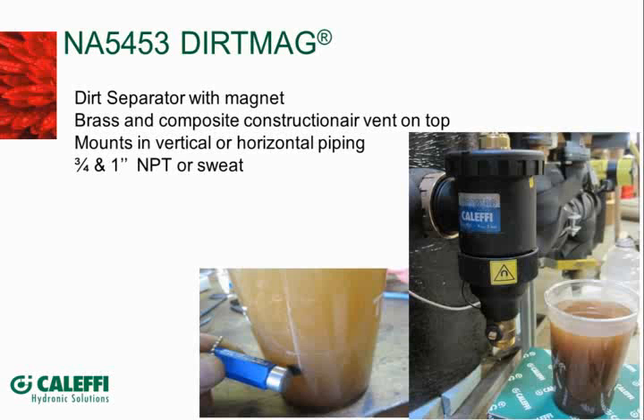Now, you're going to have to maintain it — this one's actually on my own shop, on a big solar steel tank I have. It was an old LP tank I converted into a solar storage tank. Every couple of months I go out there, put a cup under it — I'm not adding any new water, it's just debris that was in that tank when I converted it. I put a clear plastic cup under it, and you can see with the little pocket magnet in the left-hand picture the ferrous components washing out of that tank. The magnetic band on the bottom captures that. I take the band off, open the valve on the bottom, put a cup under it, and flush it out to see what comes out.